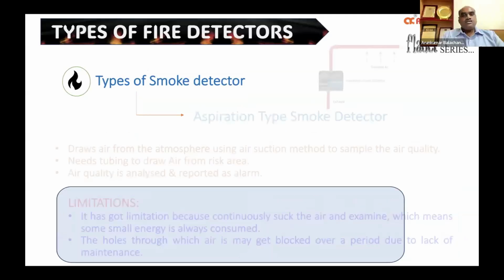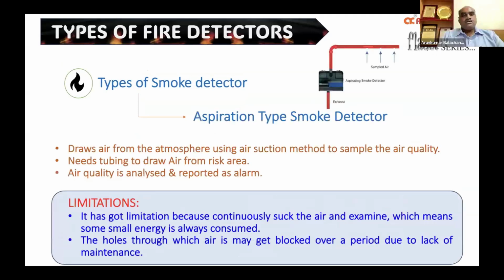The next detector we are going to see is the aspiration type smoke detector. These detectors are very widely used, especially in large data centers. Unlike spot type smoke detectors, these aspiration type detectors employ a tube and a capillary hole and use a suction mechanism for sampling the risk area air. This sampled air is checked for any smoke particles for detection of smoke. The limitation of this detector is that since there is a continuous suction of air, a small amount of energy is always consumed. Also, the maintenance of the capillary holes becomes very important, as if they get blocked, then the sensitivity and the mechanism of detection will be down.